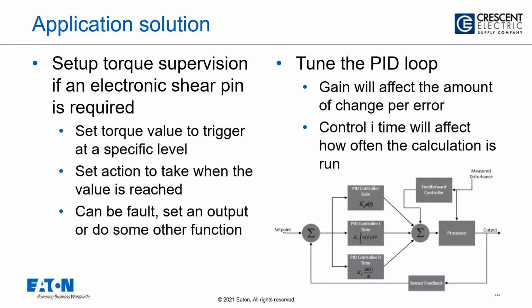And the PID wizard is shown here. Obviously it has three gains, P, I, and D, and the set point comes from the torque level or a horsepower level, and then the feedback output is wired back through the analog input, and then it comes to the drive, and that becomes the PID input. The error is amplified, regulated by the P, I and D gains, and then it controls. And there is a feed forward mechanism also, and then it controls the motor speed in order to maintain the constant torque.